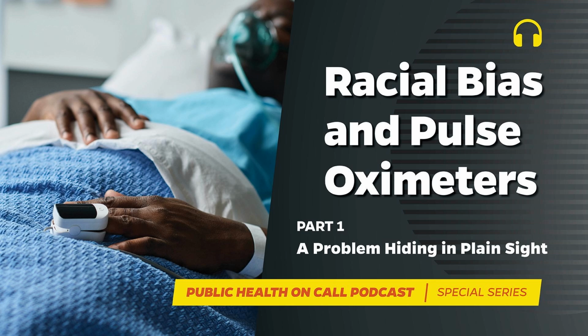Crucially, the readings could be individualized by squeezing a drop of blood from the ear and scanning it using spectrophotometry to figure out just how much light was being absorbed by the patient. This allowed the physician to personalize light level calibrations and achieve more accurate readings. Plus, clipping the device to the ear, which wouldn't lose circulation as quickly as a finger or toe, would provide more accurate readings for longer periods of time.